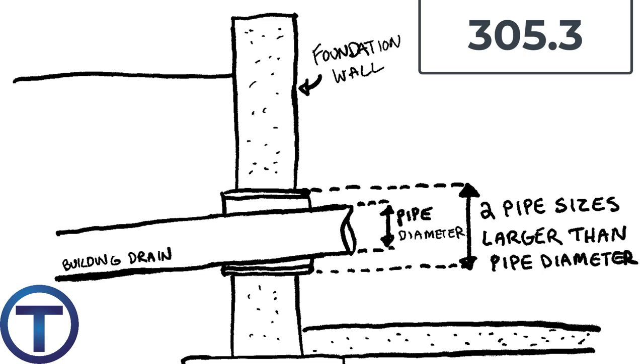305.3 tells us that when pipes pass through a foundation wall, they need an extra sleeve around them with some space, and that sleeve should be two pipe sizes larger than the pipe itself. That gets tricky — for a three-inch pipe, you'd go to four inch, then five inch, but five-inch pipe is hard to get and very expensive, so you'd go to six inch, which leaves an enormous gap that can let groundwater in. We do have to seal these pipes through a foundation so groundwater won't come into the building. For test purposes: the sleeve is two pipe sizes larger than the diameter of the pipe passing through.